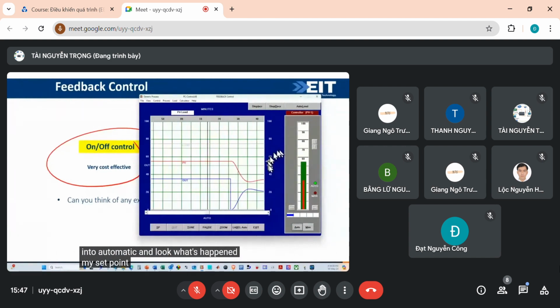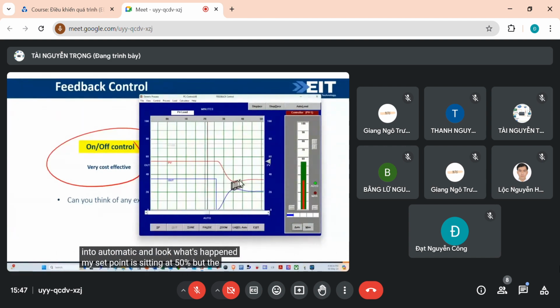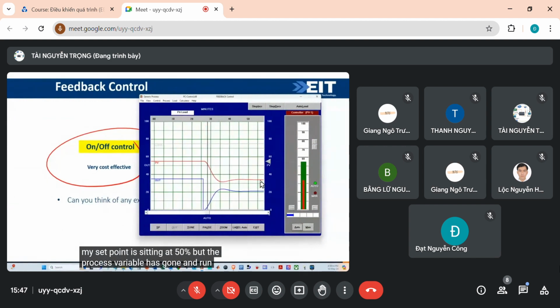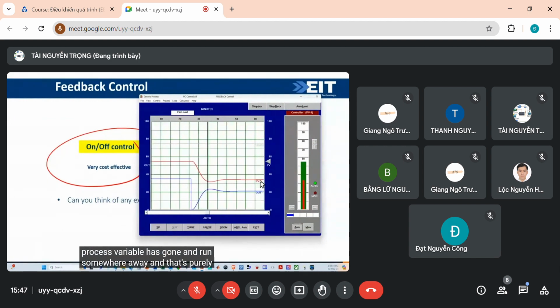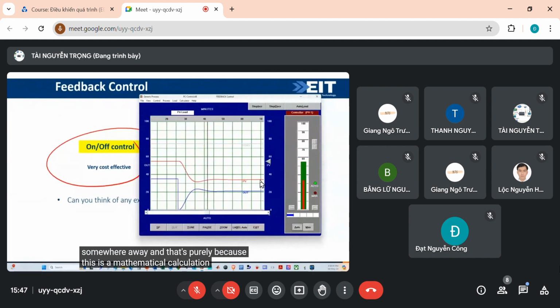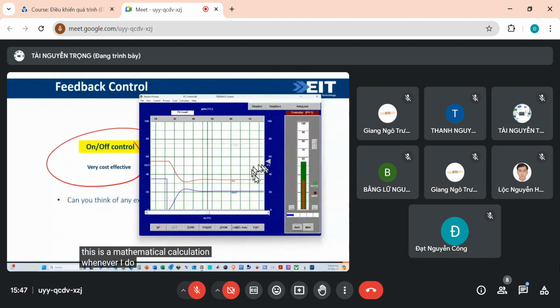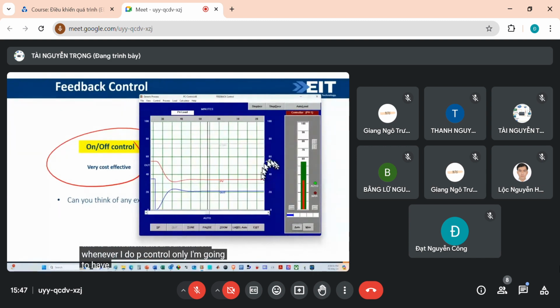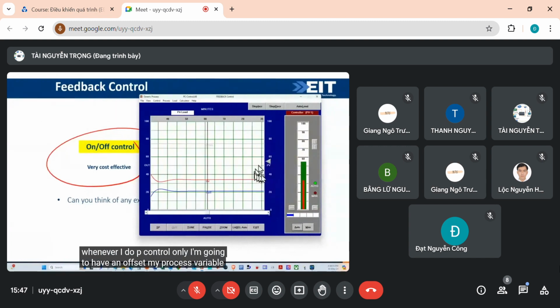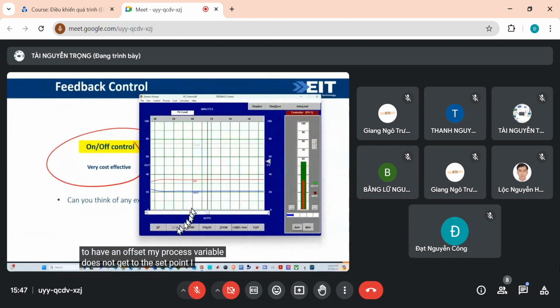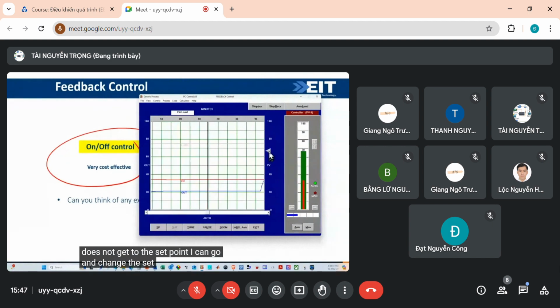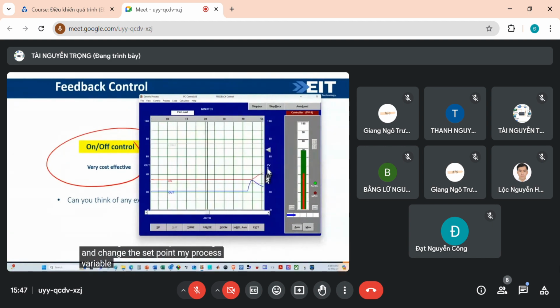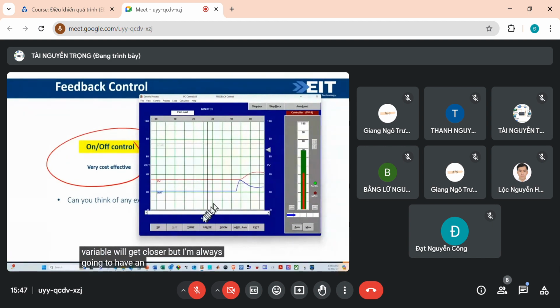My set point is sitting at 50%, but the process variable has run off somewhere else. That's purely because this is a mathematical calculation. Whenever I do P control only, I'm going to have an offset - my process variable does not get to the set point. I can change the set point and the process variable will get closer, but I'm always going to have an offset.